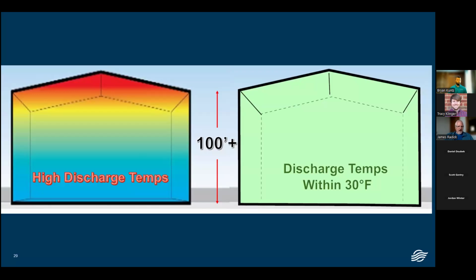So, highlighting again, high discharge temperatures. With that, you get cold air coming in near the floor. It pushes high temperature air up because you get that oil and water effect. The greater the density difference is, the more the energy basically repels itself, et cetera. You want that hot air to rise. Discharge temperatures within 30 degrees are the ones that are going to give you even temperatures. Along with the positive pressurization, you can count on your space temperatures to be within a degree or two, wall to wall, floor to ceiling, and even in 100-foot buildings.